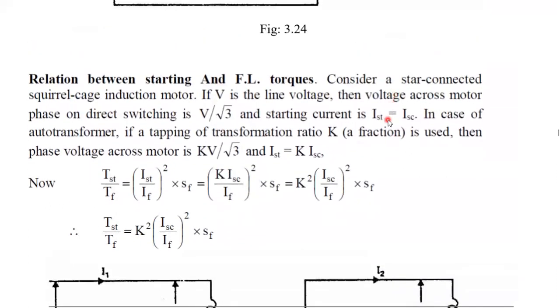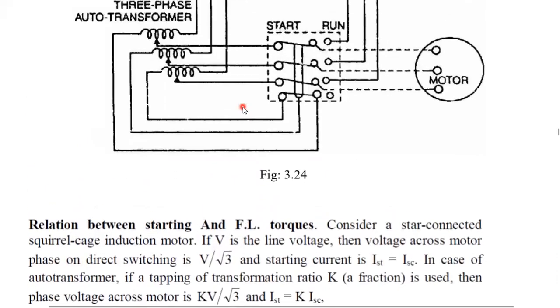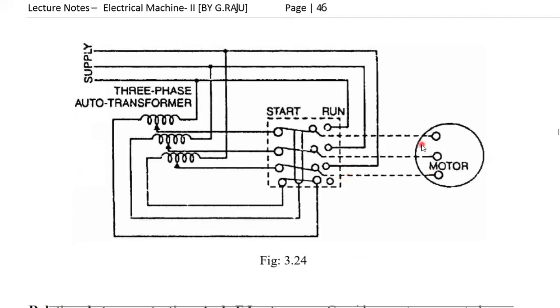At the time of starting, the phase current is equal to the line current. Line current is equal to phase current in a star connected system. In the case of an auto transformer, the tappings have a ratio K. So by using an auto transformer, we control the induction machine's starting.